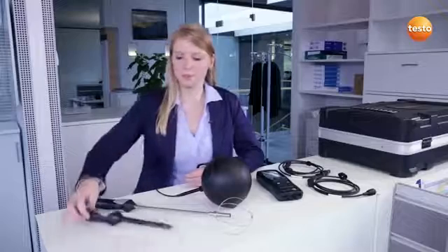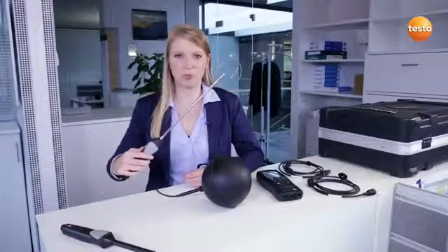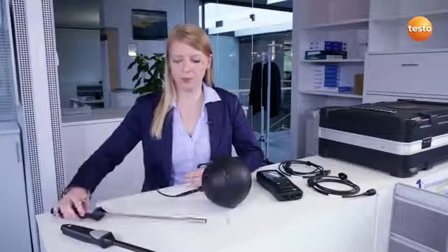In order to carry out the measurement, I need the following measuring equipment: the ambient air humidity probe in order to measure the ambient air temperature and humidity, the comfort probe to be able to evaluate the airflow in the room, and finally, I need the globe probe to measure the radiant temperature. An acclimatization period of 20 to 30 minutes must be observed here. I've connected all the required probes to the Testo 480. I place everything together on the tripod.